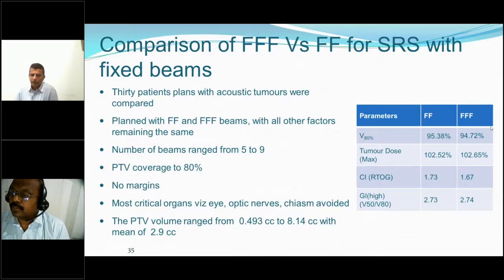There is a question: any special chamber recommendation for FFF beam commissioning? Whatever I said, you can use a regular Farmer type, but make sure the ion chamber you use is suitable for the high dose rate, and that for the profile there is no volume averaging effect. You have to check those two, that's all. Otherwise, you can use any Farmer type chamber for an FFF beam. Only thing is, when you go for high dose rate, it should be able to measure.